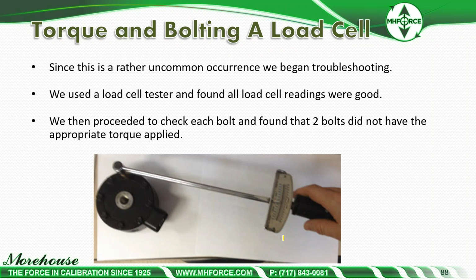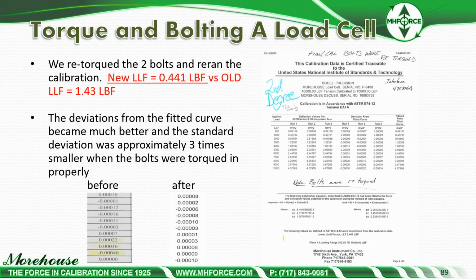What ended up happening is the person that was putting it together painted everything, torqued everything, and didn't realize they missed 2 of the bolts. They painted everything. That became hardened, and no one suspected anything different because it was hand tight versus torque specification. What we ended up finding out is that the 2 bolts broke loose counterclockwise a lot easier than the other ones. So we retorqued everything. After we did that, we found the new deviation was 0.441 pound versus the old, which was 1.43. This was with bolts that were torqued.